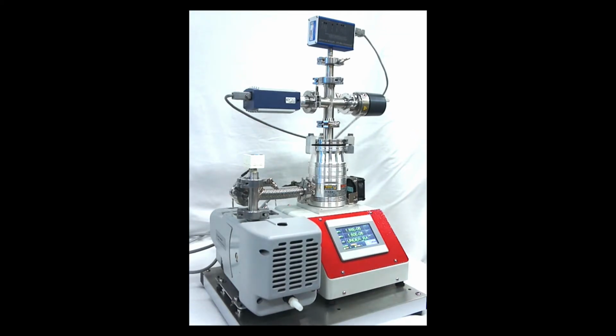Last but not least, the most powerful controller units on the market. It not only can drive and control the turbo pump, it can also drive and display the pressure data from the vacuum gauges. And there are 14 types of vacuum gauges on the market which are compatible with this controller. Like for this demo, we use GP275 and Agilent FRG700 full-range cold-cathode gauges and Inficon BPG full-range vacuum gauges.